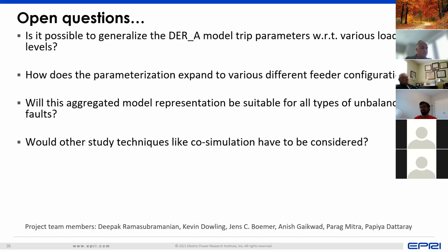Definitely the concept can be carried over, especially the tripping aspect, because that's just voltage dependent. But these aspects of how you would control the reactive power, how you would do voltage support, and how you would prioritize between active power and voltage support, will they be really symbiotic with each other? Those are things that have to be kept in mind when you start looking at parameterization in the DC grid.